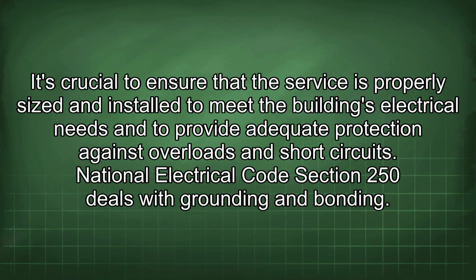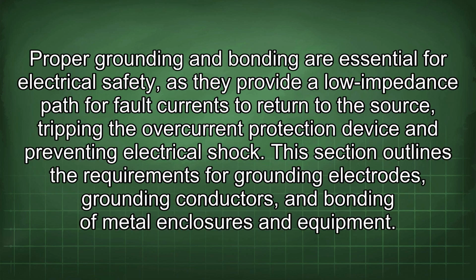National Electrical Code Section 250 deals with grounding and bonding. Proper grounding and bonding are essential for electrical safety, as they provide a low impedance path for fault currents to return to the source, tripping the overcurrent protection device and preventing electrical shock. This section outlines the requirements for grounding electrodes, grounding conductors, and bonding of metal enclosures and equipment.